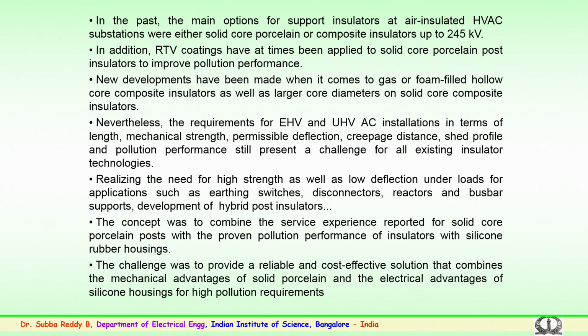Realizing the need for high strength as well as low deflection under loads for applications such as earthing switches, disconnectors, reactors, and bus bar support insulators, this gave way to the development of a new type of insulator, the hybrid post insulators, which are being used in high voltage EHV or UHV substations.